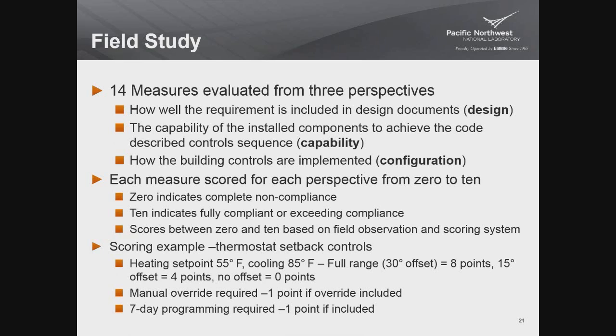So what we did in the field work is we evaluated these 14 measures from 3 perspectives. The first perspective is how well the requirement is included in the design documents. We call that the design perspective. The second perspective was the capability of the installed components to achieve the described control sequences. That's capability. Could it function the way that the code wants it to? And then finally, how the building controls are actually implemented in those buildings. How are they actually working? We call that the configuration perspective.